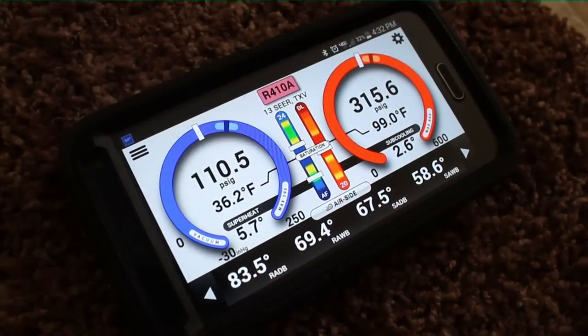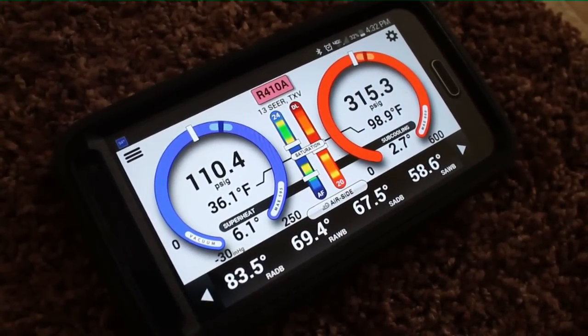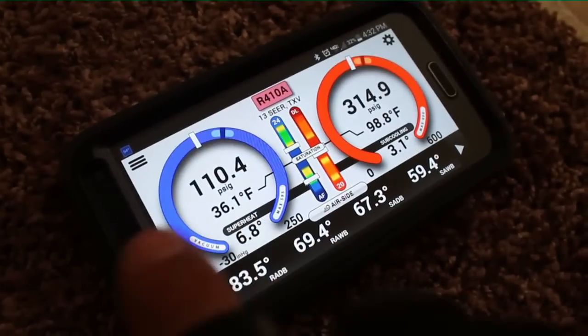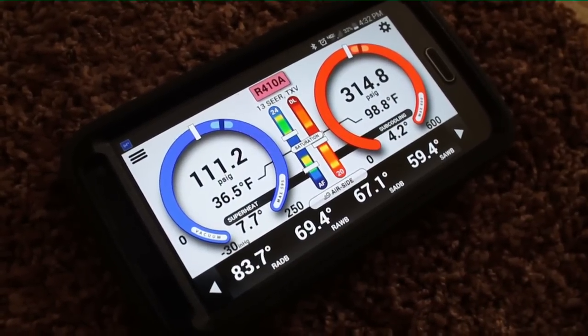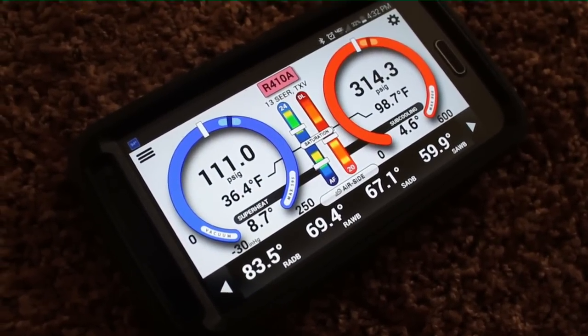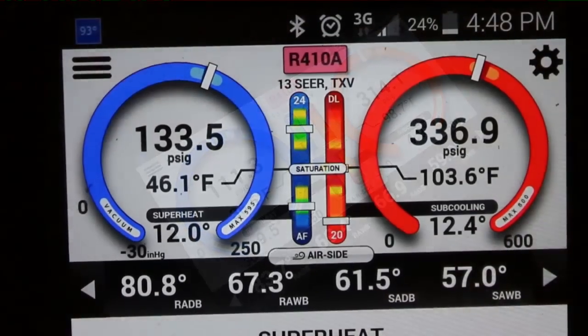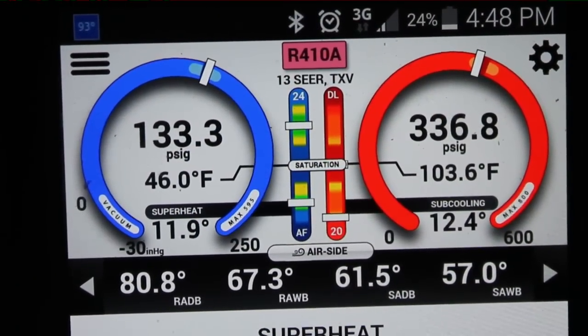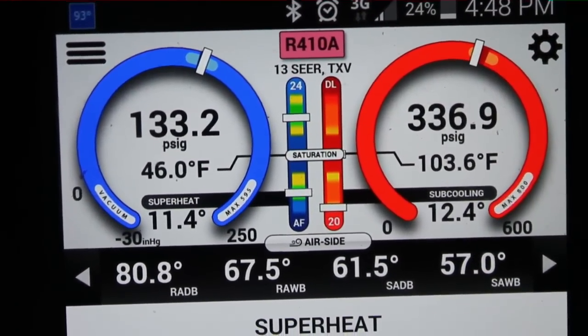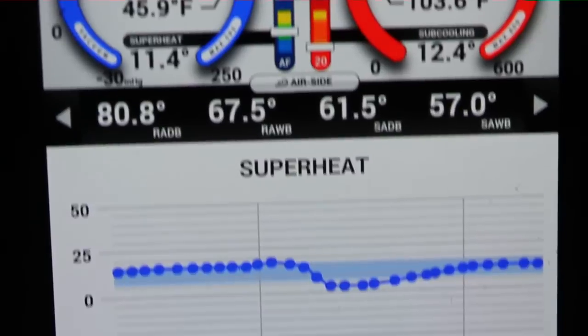As you see, the pressures are very low, and they changed quite a bit because I took the door off. Our suction pressure plummets. Everything changes, so we'll let that settle out, let it run for a few more minutes, check and see how the TXV responds. As you see, after we made our adjustment, we have a little bit better as far as superheat and subcooling. 12.4 subcooling, 11.4 superheat.